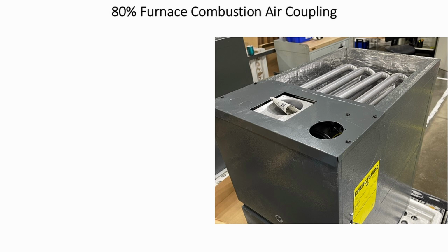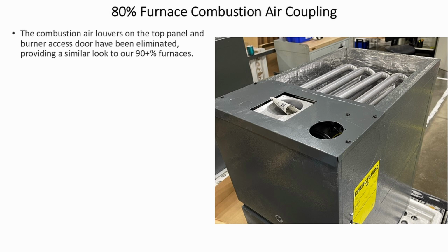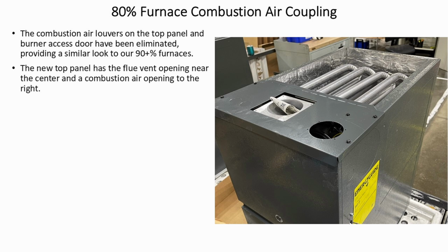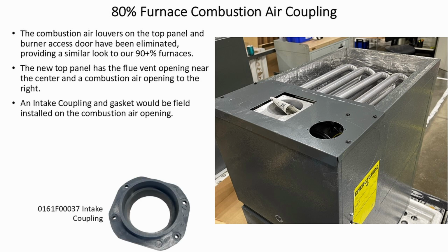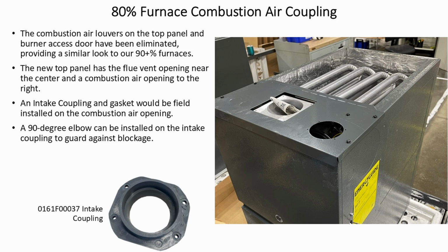80% furnace combustion air coupling. The combustion air louvers on the top panel and the burner access door have been eliminated, providing a similar look to the 90% furnaces. The new top panel has the flue vent opening near the center and the combustion air opening to the right. An air intake coupling and gasket would be field installed on the combustion air opening. A 90-degree elbow can be installed on the intake opening to guard against blockage.